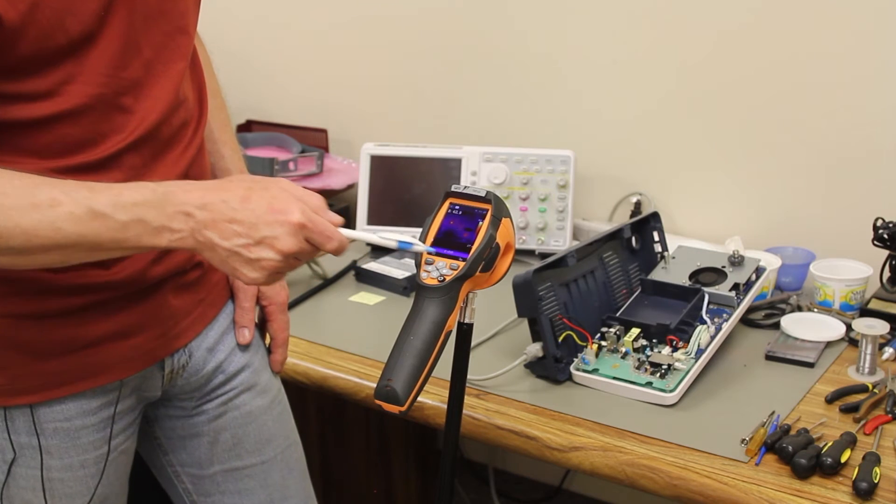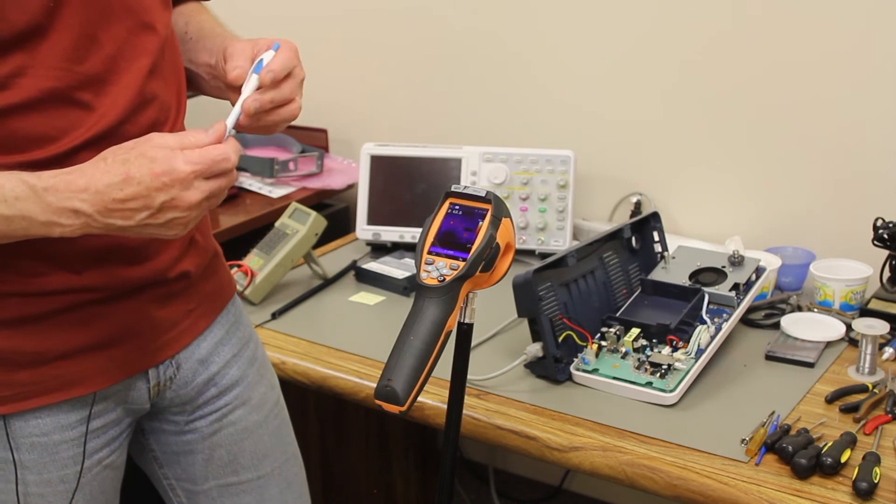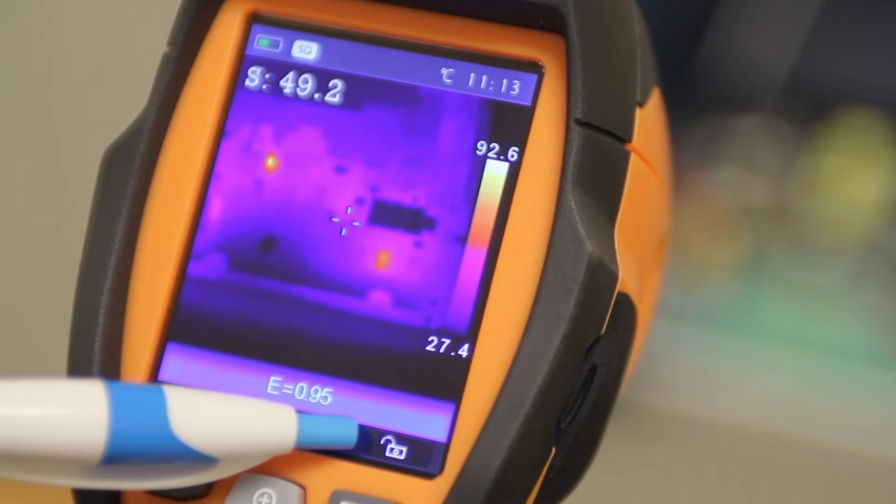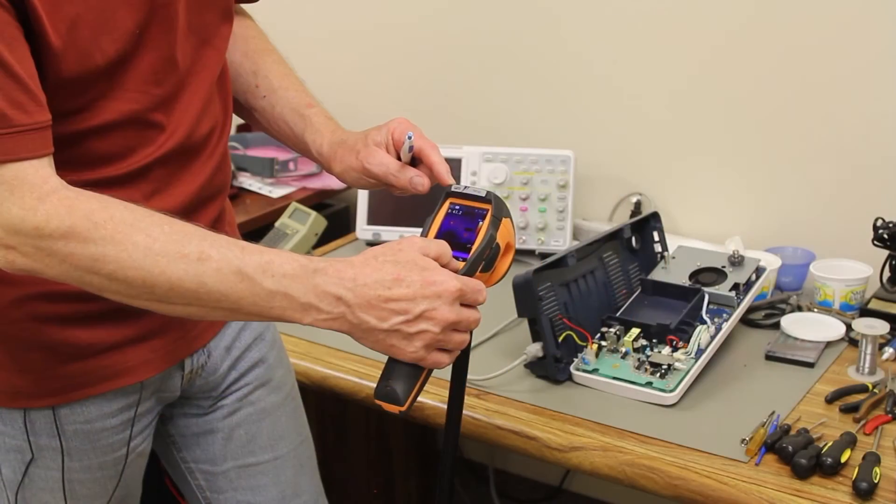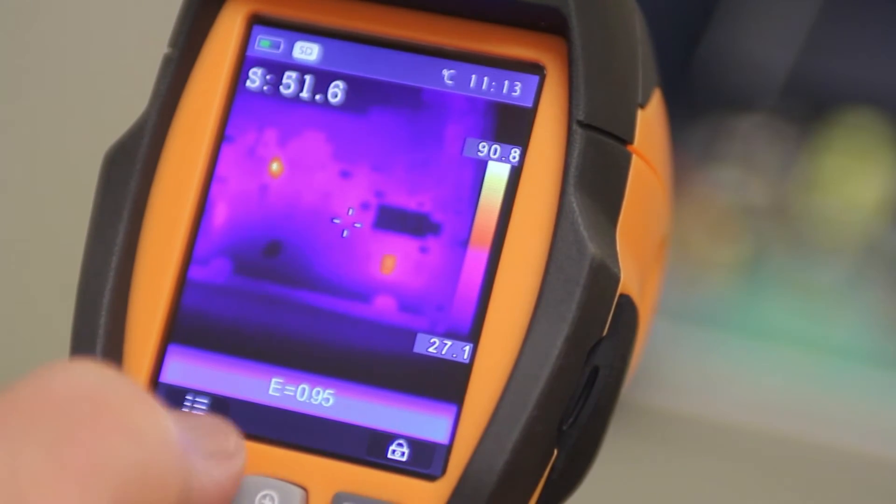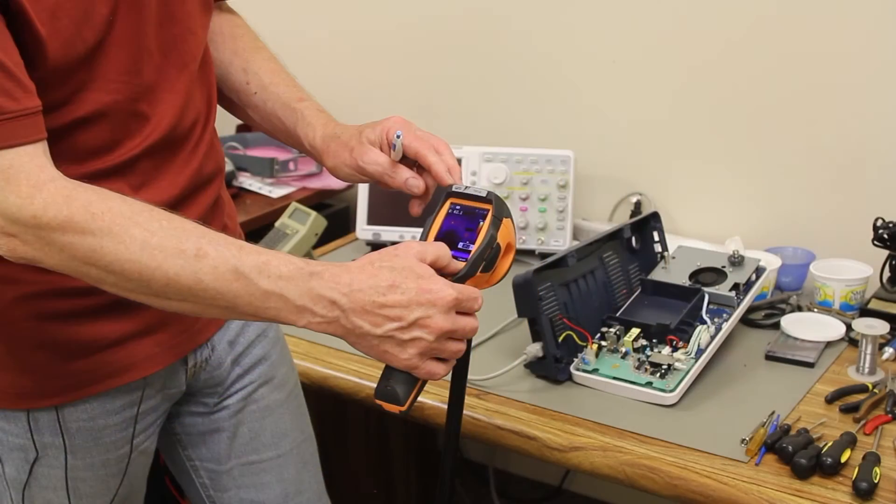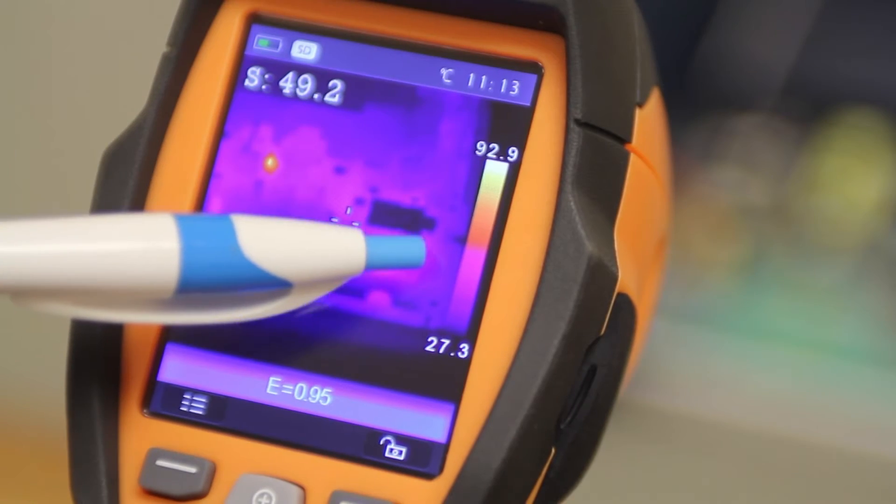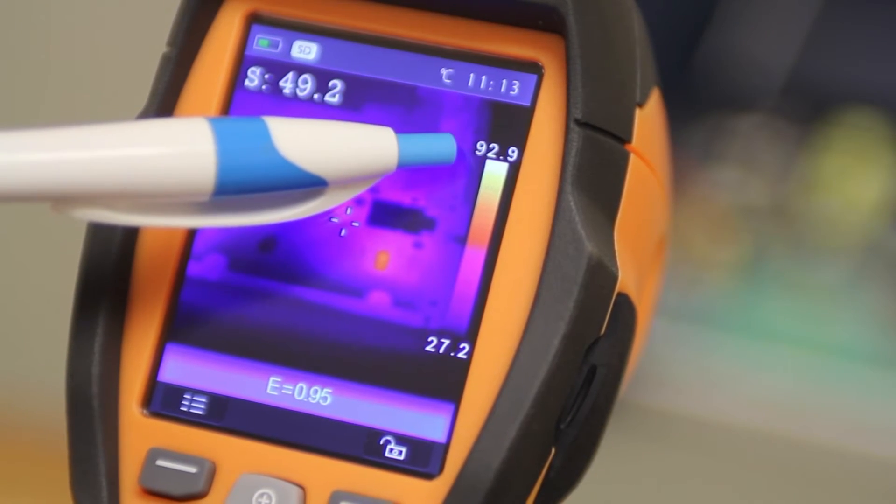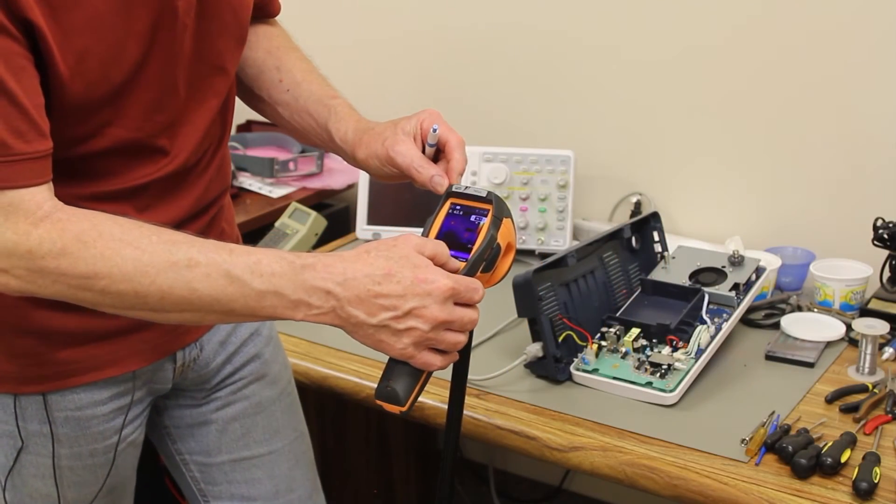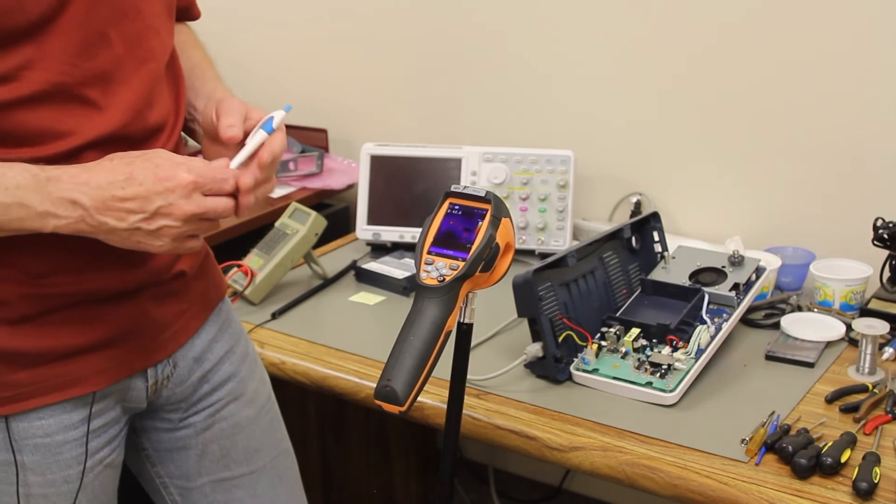This button here is your automatic and manual button. Right now the little key lock symbol is open so I'm in automatic, and if I close this or if I hit the button again the key lock closes and now I'm in manual mode. And if I hold manual mode for a couple of seconds then you get the ability to set your lower limit and your upper limit of the temperature scale that you want to enter manually. So I'm going to cancel out of that and get back to automatic mode.